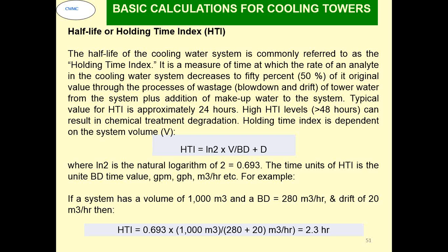As an example, suppose the system has a volume of 1000 meter cube, a blowdown of about 280 meter cube per hour, and a drift of about 20 meter cube per hour. Then the holding time index works out to about 2.3 hours. We will discuss subsequently the significance of this in terms of cooling water treatment.